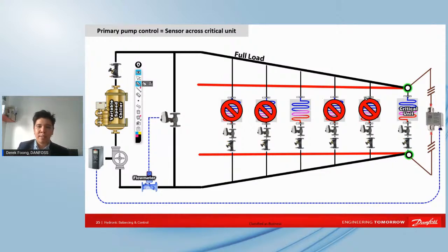All right. So again, I repeat that. If we keep the pressure constant across the critical unit, the rest of the units in the system actually achieve more pressure than required, even during partial load. All right. But of course, the biggest challenge will always be how to locate this critical unit, right? So we won't go too deep into that now.